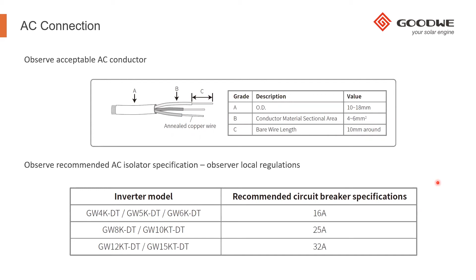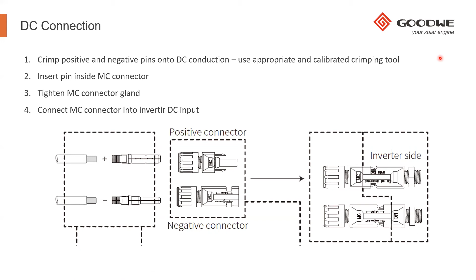In terms of the DC connection, for all inverters for Europe, we do provide MC4 connectors. We provide the positive and the negative connectors. Usually what you do is crimp the positive and negative pins onto the DC conductor. It is important, and I must highlight, that you use the appropriate calibrated crimping tool. Use a crimping tool that is recommended or authorized by Stäubli or MC multi-contact. This will minimize the frequency of failures with regards to crimping. All you have to do is insert the pin into the MC4 connector, tighten the connector gland, and then connect the connector into the inverter side of the inverter.